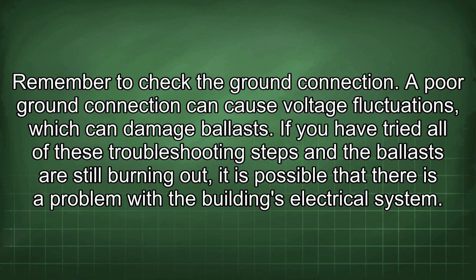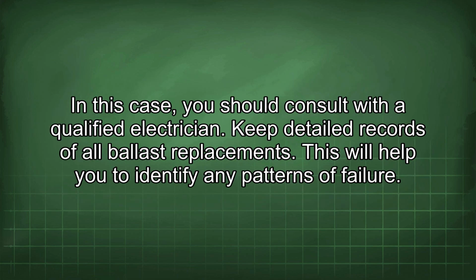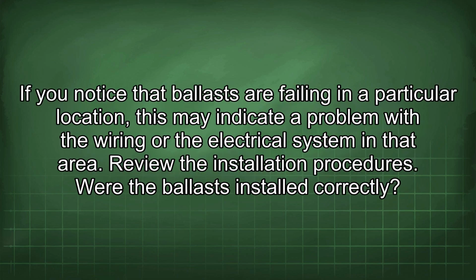If you have tried all of these troubleshooting steps and the ballasts are still burning out, it is possible that there is a problem with the building's electrical system. In this case, you should consult with a qualified electrician. Keep detailed records of all ballast replacements. This will help you to identify any patterns of failure. If you notice that ballasts are failing in a particular location, this may indicate a problem with the wiring or the electrical system in that area.